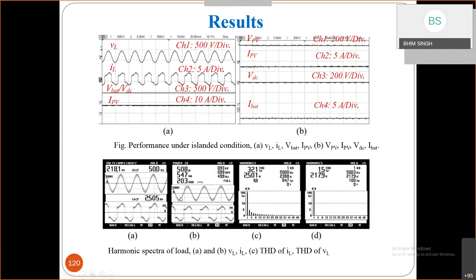And when it is connected to the grid, within 3 to 4 cycles, standard say 10 cycles, we are able to connect it, and the load voltage and load current are not affected. So after 3-4 cycles, we are able to synchronize to the grid well. After the grid appears and the inverter exchanges power with the grid at unity power factor, you can clearly see the current is put into the grid, and the THD of the grid current is again reduced to 1.4%.